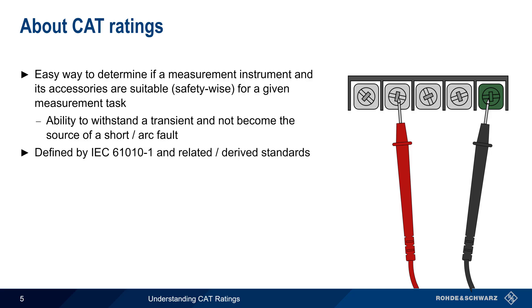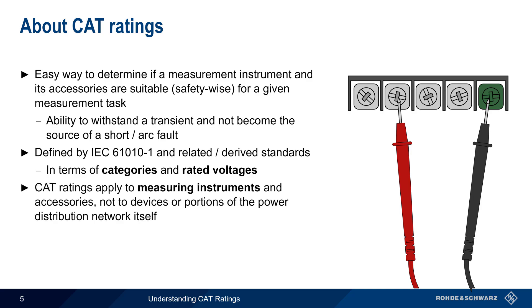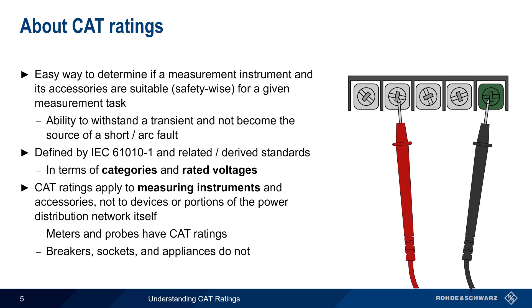CAT ratings are defined by IEC 61010-1 and other related or derived standards. It's very important to remember that CAT ratings apply to measuring instruments and their accessories, not to devices connected to the power distribution network or parts of the distribution network itself. Meters and probes have CAT ratings, but things like breakers, sockets, and appliances do not.